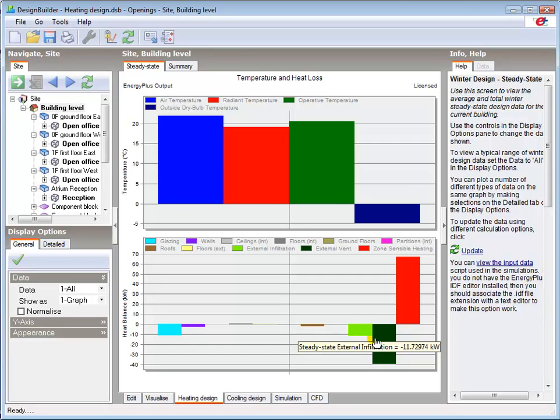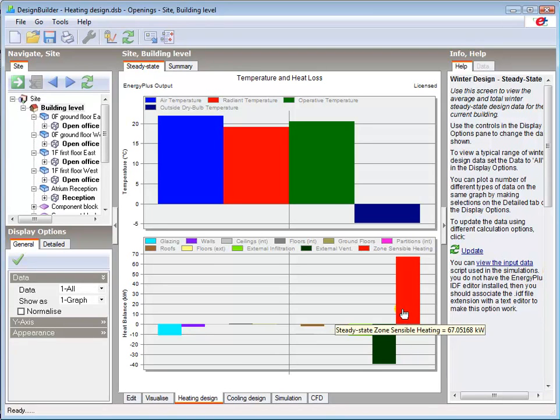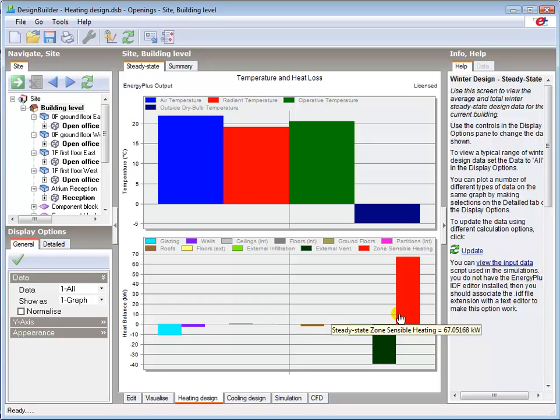The ventilation load remains constant as this is set to minimum fresh air per person so is dictated by occupancy density and the specified minimum fresh air rate. The total impact of these changes is that the building heat loss is reduced by around a quarter to 67 kilowatts.